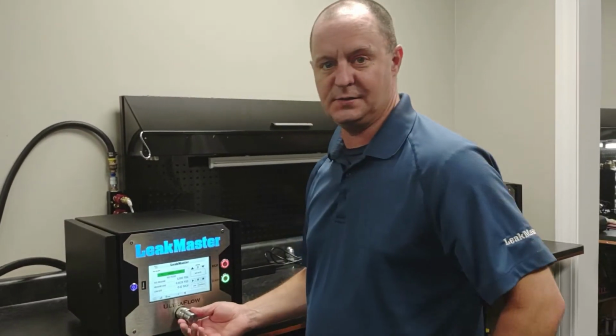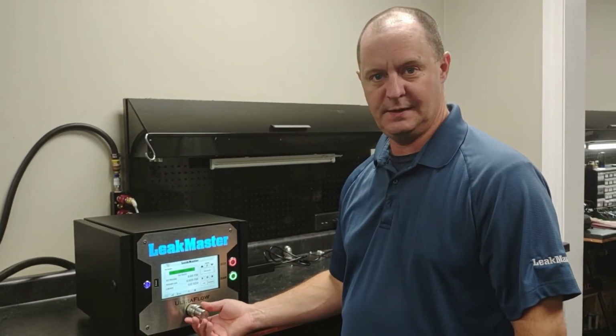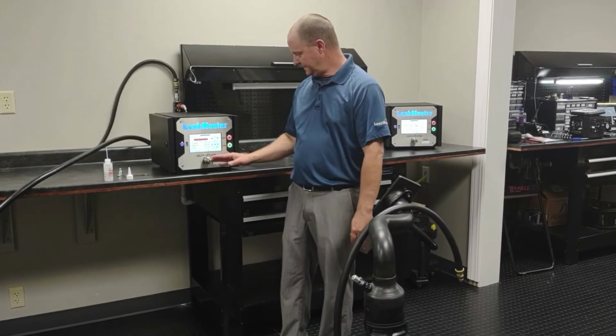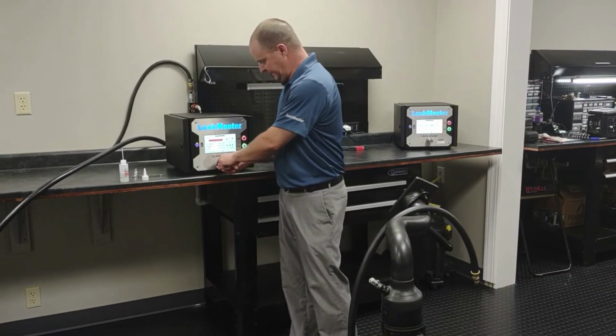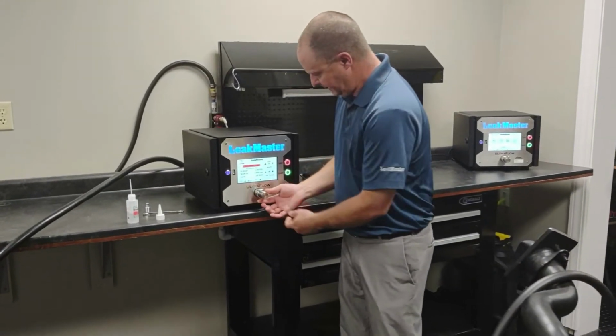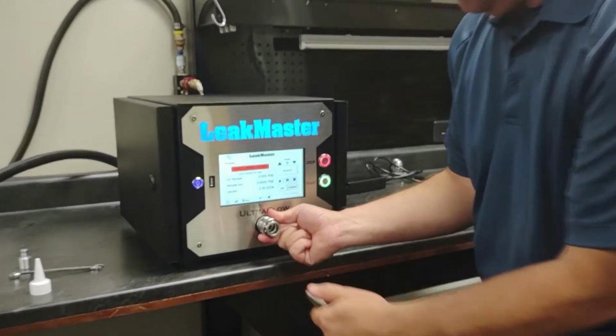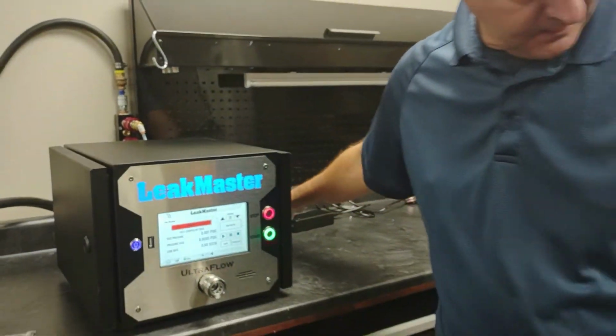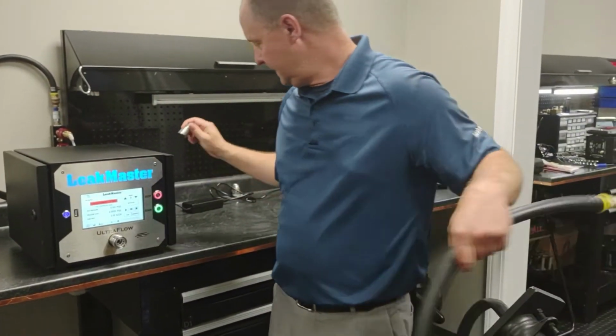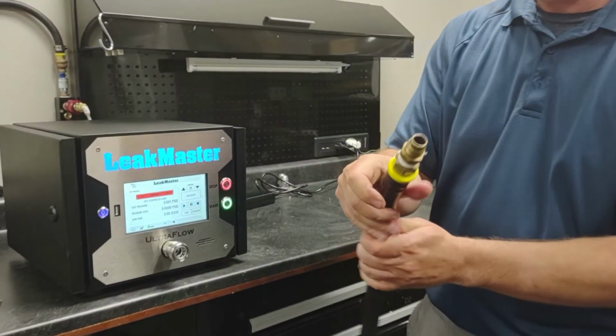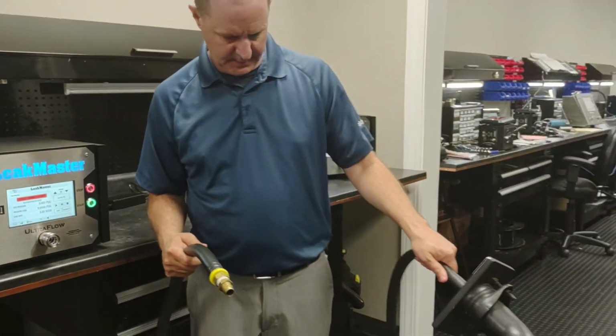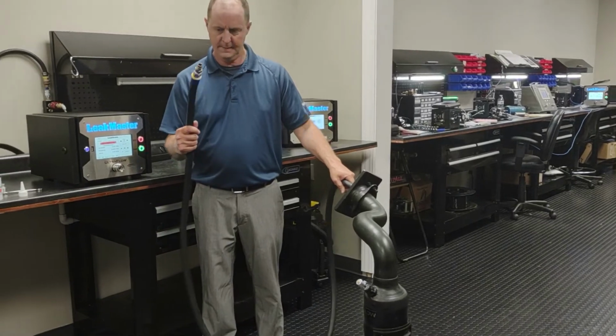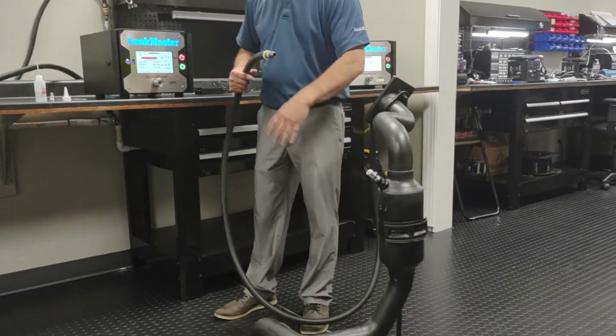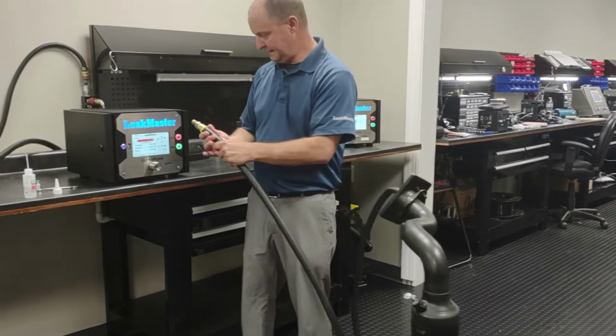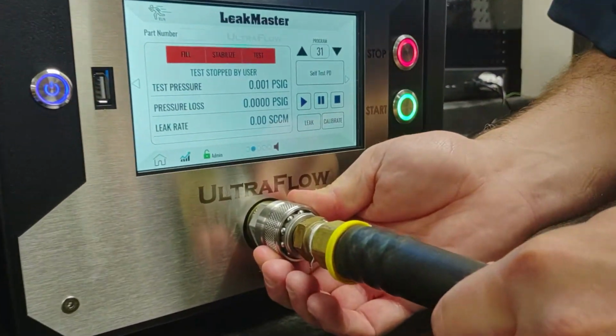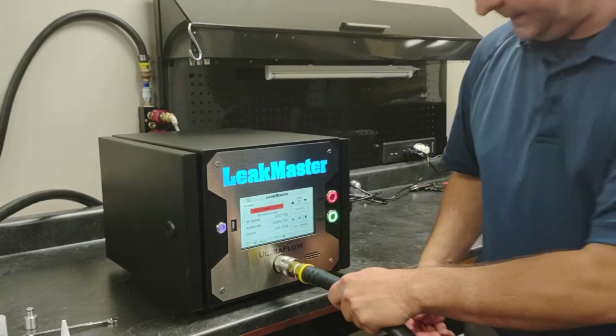So now we are ready to actually plumb up to our test part and start troubleshooting our fixturing setup. Now that we've done a self-test and verified that our internal manifold is leak-free, we're going to remove the plug from the front. You're going to do that by sliding the sleeve forward and pulling the plug out. Make sure you keep this with the station, because this is good for troubleshooting. We are plumbed up with an automotive exhaust component here, and we're already sealed up. We've got some manual seal tooling tied to this, and I'm going to take my air line and plug it into the front of the UltraFlow, and make sure it's locked in place.